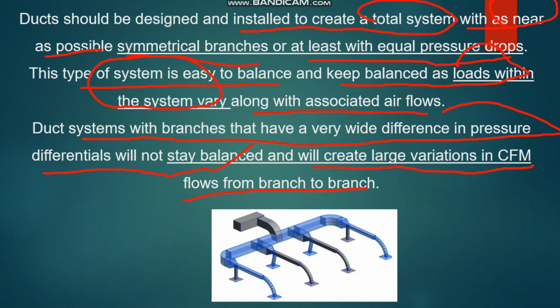So for example, like you see here, if you take the branch here, we have taken proper equal branches. In this case the system will be properly balanced, so there will not be much difference in flow and pressure differential. On site we normally try to do this type of design, and although it is not possible on every site, we will try our best to make equal pressure drop and equal pressure differential.